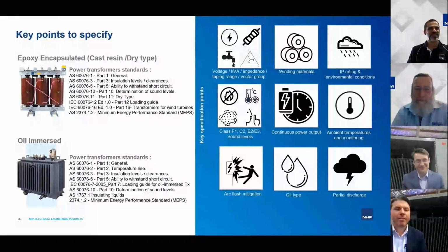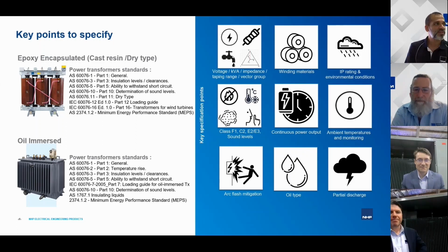All right. So if I was an end user or a consultant trying to specify a transformer, we just wanted to quickly run through some of the key characteristics that you really want to make sure you're putting in your specification. Some of the main things to consider: as you can see on the slide, there are a lot of different ratings or standards, mainly coming out of the AS 60076 standard and some out of the IEC, depending on what type of transformer you look at. Those are some of the standard considerations you should refer to within your specifications.